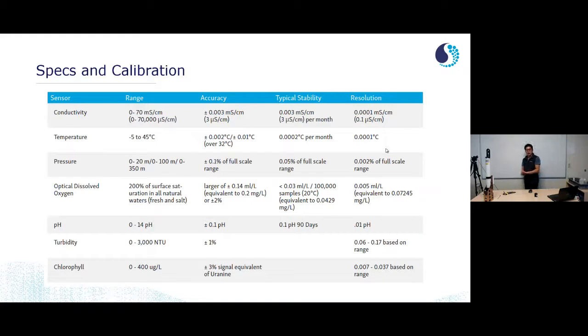Okay, so really quickly I want to take a look at the specs and calibration of this instrument. As mentioned before, it's a multi-parameter instrument with lots of different sensors. You have your base conductivity, temperature, and pressure that you have with other Seabird CTDs. This also has an optical dissolved oxygen sensor, the SBE63, with the same specs as the SBE63 you have on your 37 SMP ODOs from Seabird. Maybe you have an SBE63 installed on a 16 plus V2 moored CTD — exact same sensor, exact same specs.